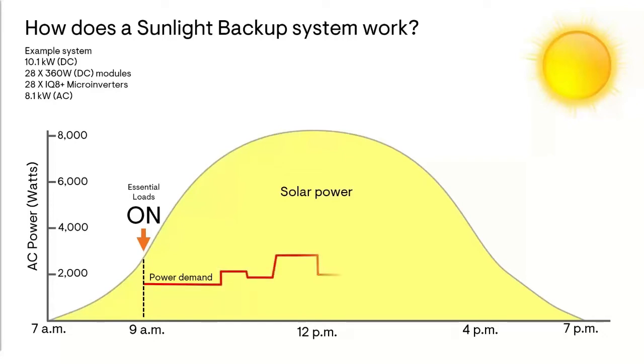The load control algorithm will allow the essential loads to turn on one at a time with a gap between them. These gaps between the loads powering on allow the system to identify if there are any problem loads, and if there is a load that's causing repeated collapse of the microgrid, after 5 failures it will stop attempting to power that load for the rest of the day. Then, in order to prevent the homeowner from experiencing that kind of on-off power cycling at the end of the day, the load control algorithm will disconnect the essential loads at 4 p.m.